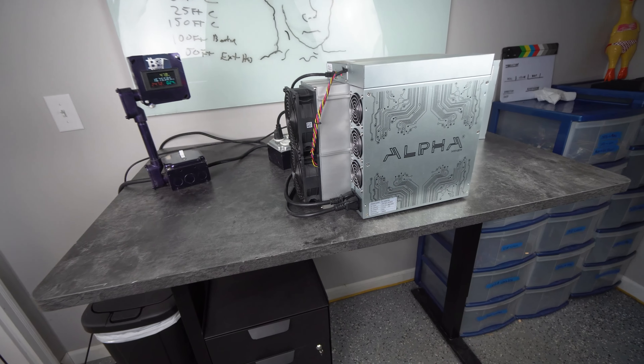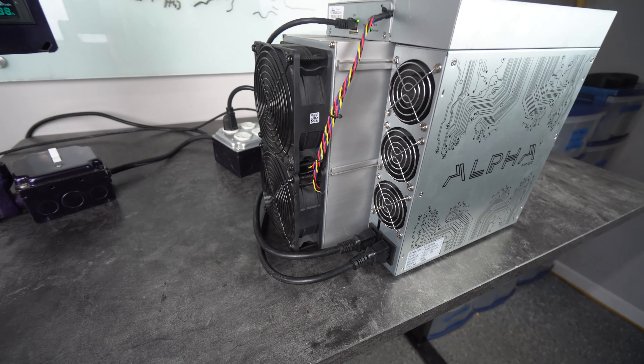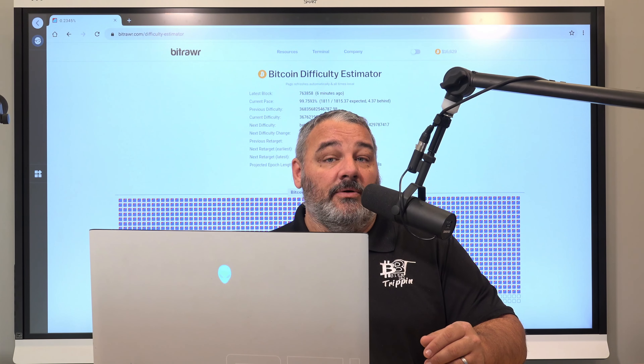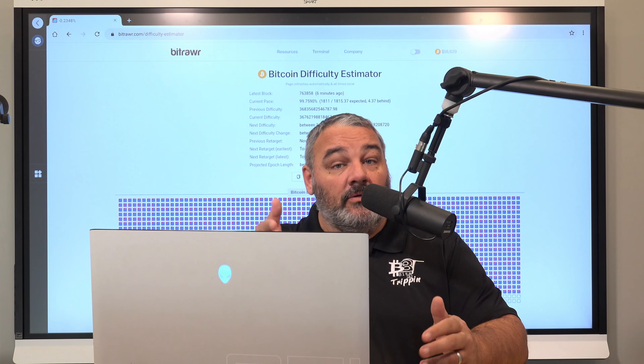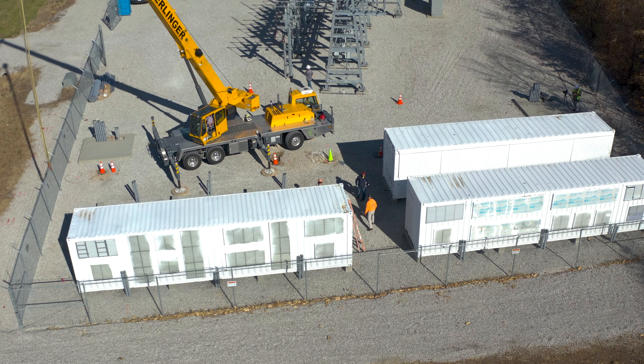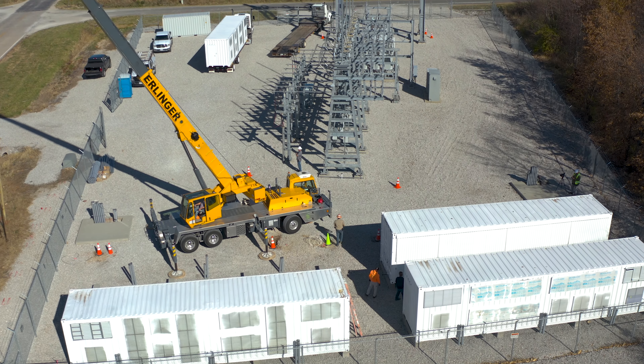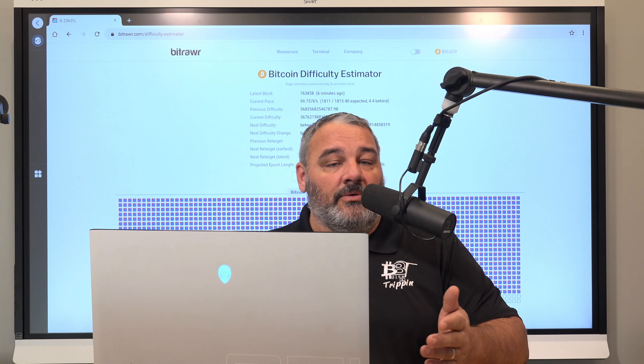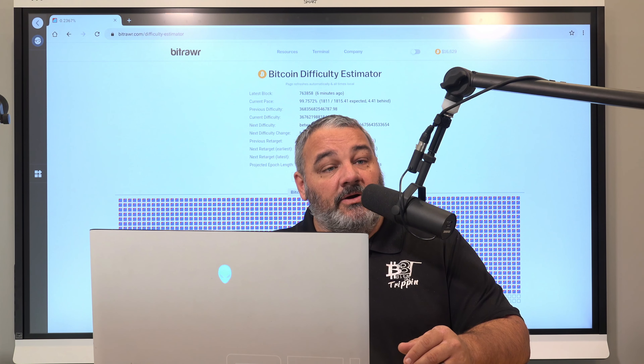This is what we call a medium-tier power setup. Typical setups run at 208, 220, or 240 volts, which means you're coming down from 415V. This is a little different — we're coming in at 480V direct. This is why we did the video on the Alpha Miner power supplies, to show that they can support the 277-volt input. Coming from 277V single-leg — taking three-phase down to single-phase — gives us more overhead on total wattage and power draw if we want to overclock these units without stressing the system.